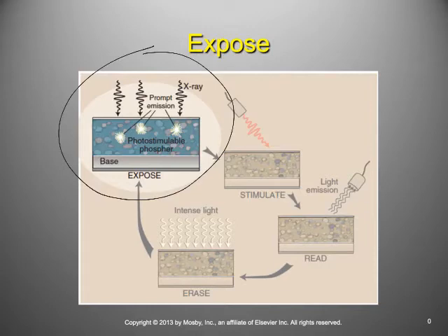So the significant thing here is that these electrons, even though they're metastable, want to return to a grounded state. So if we do not immediately develop a CR image receptor after exposure to X-rays, we will lose our image. The textbook says in about 8 hours, the image will fade to where it's no longer registerable by the reader.